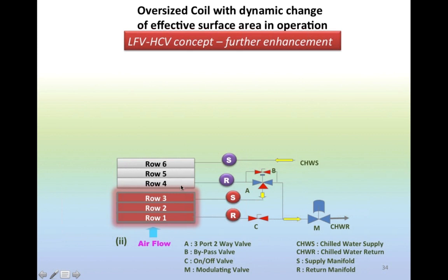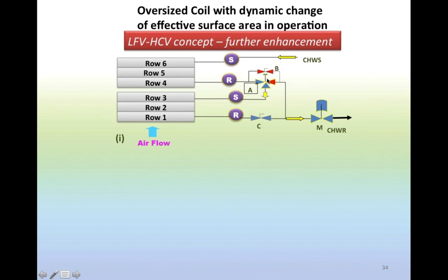I supply to row 6 and pull out the water from row 4, so only 3 rows of a 6-row deep cooling coil are functioning at this stage, which is what I discussed with you in the table as well. Going from a 6-row down to a 3-row at part load, you'll get a much lower sensible heat ratio of the cooling coil. So this is a strategy, and it's very simple. We've got a 3-way kind of bypass valve here. Earlier, I made sure that this particular valve was closed.